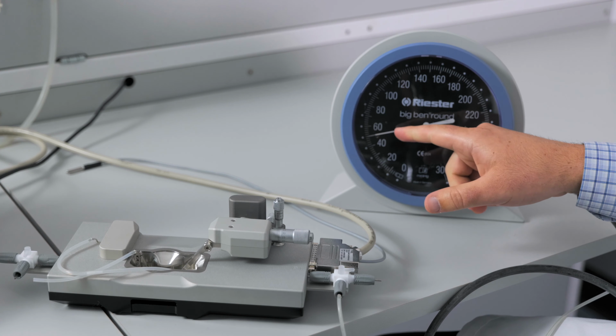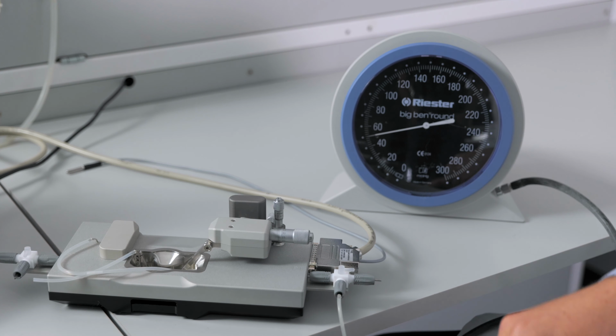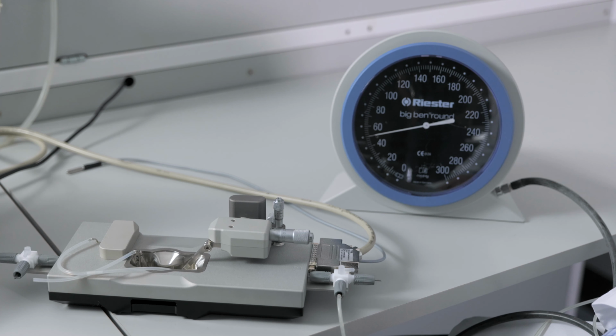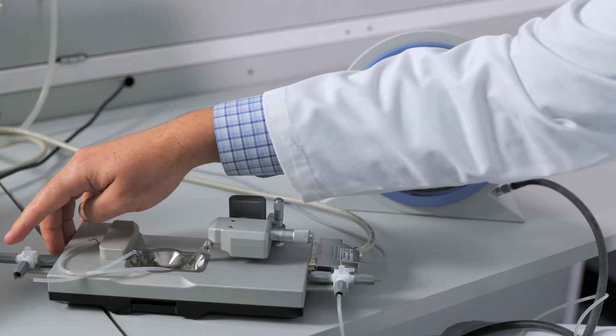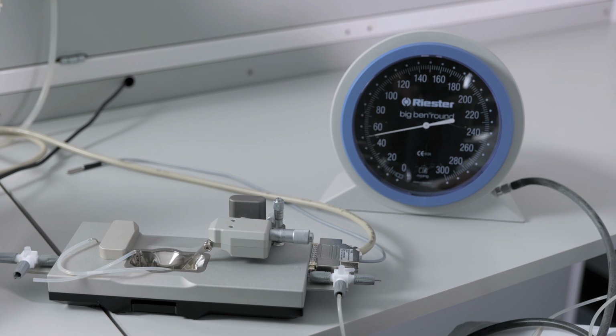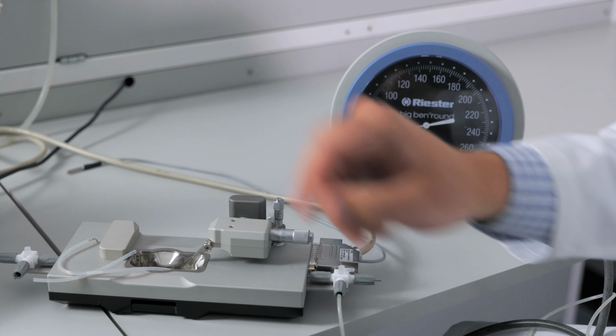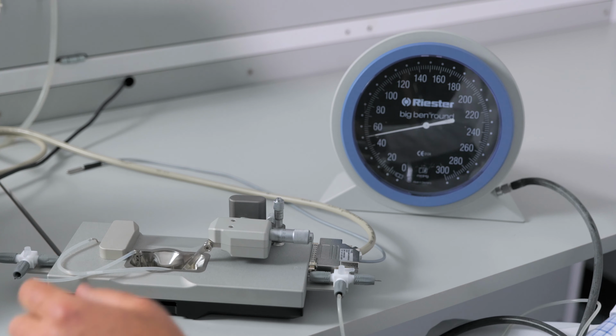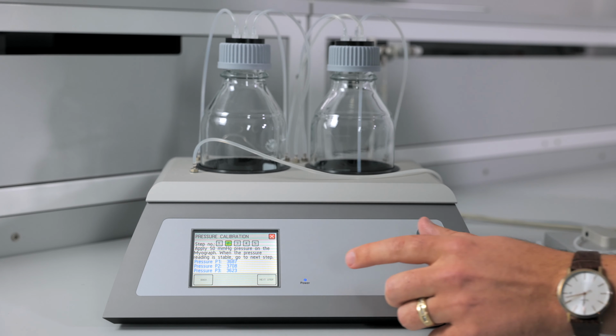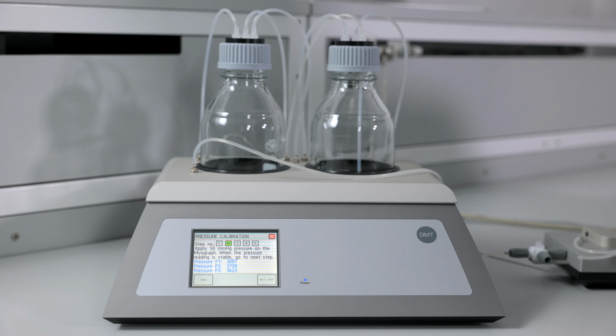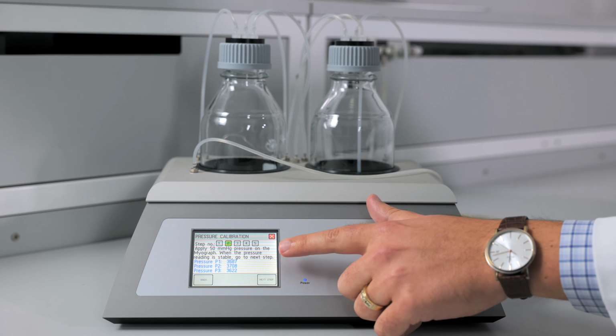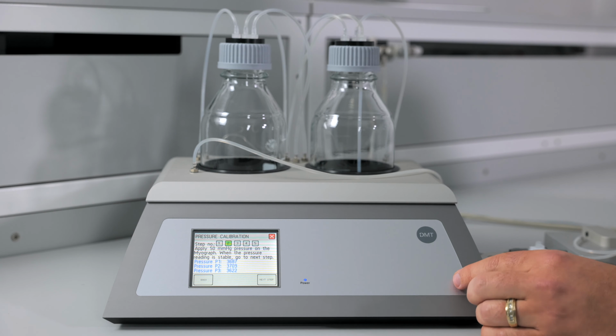And pressure should be holding. It is here, which is good. If you are losing pressure, that means you have a leak somewhere. It could mean that you have the three-way valve in the wrong direction, your bottle cap not tightened, or a leak in the tubing. But the pressure is holding at 50, and you can see the P1, P2, and P3 pressure readings have all increased. At each step, you want to make sure that the readings are increasing similarly. So these are all in the 36 to 3700 range, which is good.